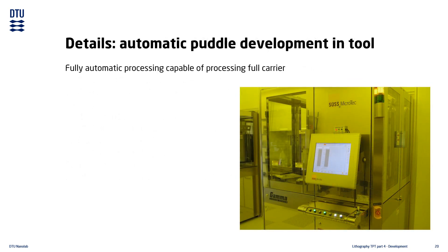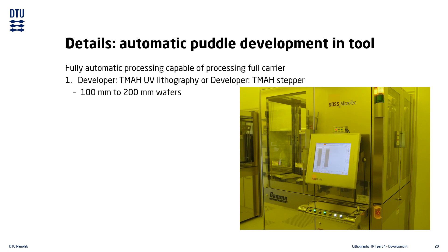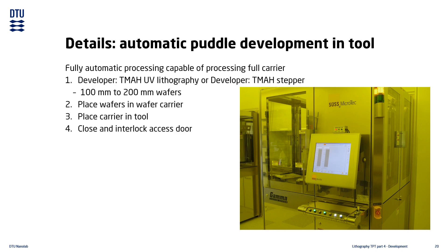Our two automatic developer tools also only process a single wafer at a time, but can process an entire wafer carrier automatically. Both tools use TMAH as developer and can only process whole wafers from 100 to 200 mm in diameter. You place your wafers in a wafer carrier, put the carrier into the machine, select the process you want to run, and press start. When the process completes, you remove the wafer carrier from the tool.